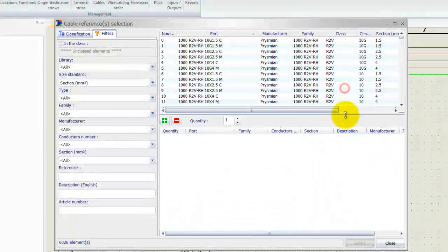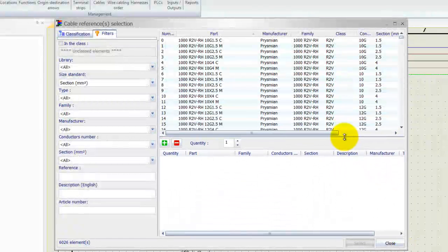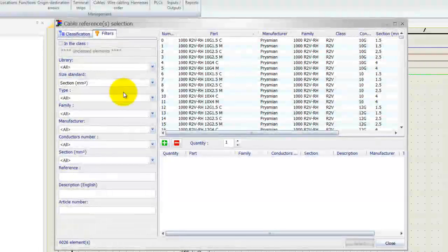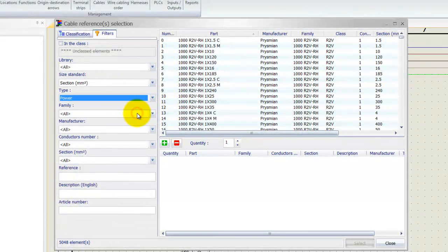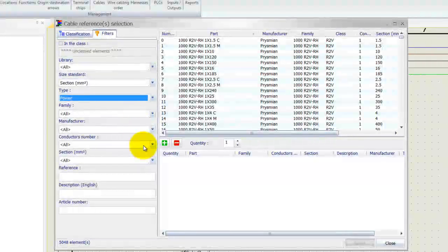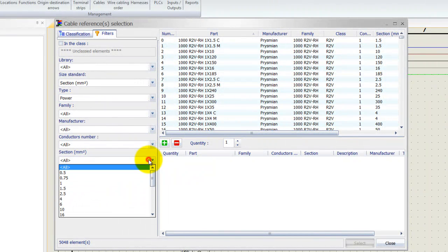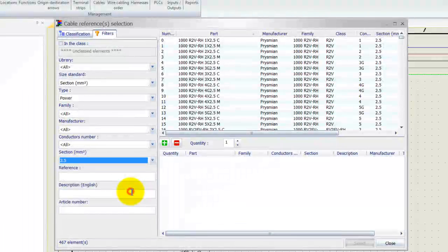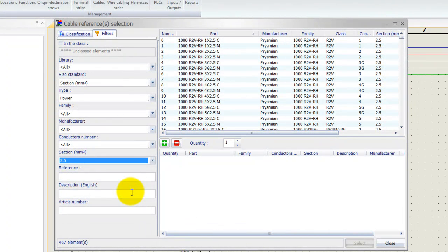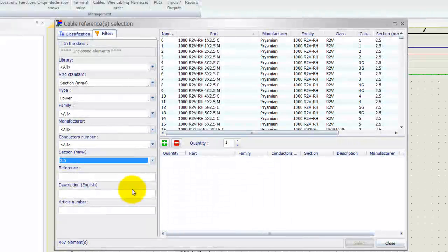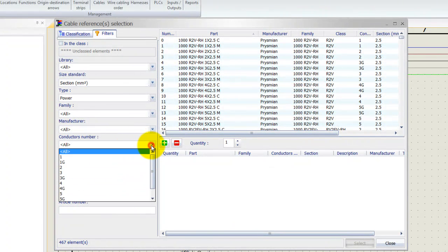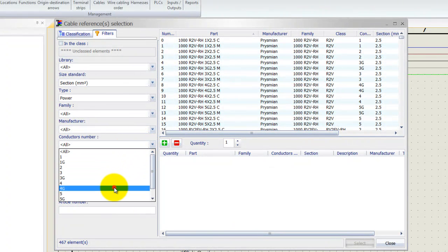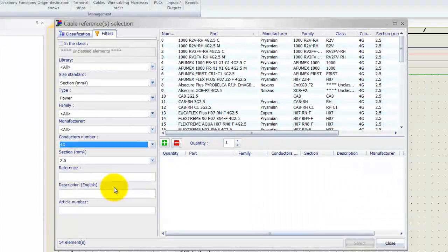Now I'm going to filter out for some cables here. I might want to have a power cable, and the section say three kilowatt, so should be alright for a 2.5 millimeters squared. And the number of conductors should be four with a ground.